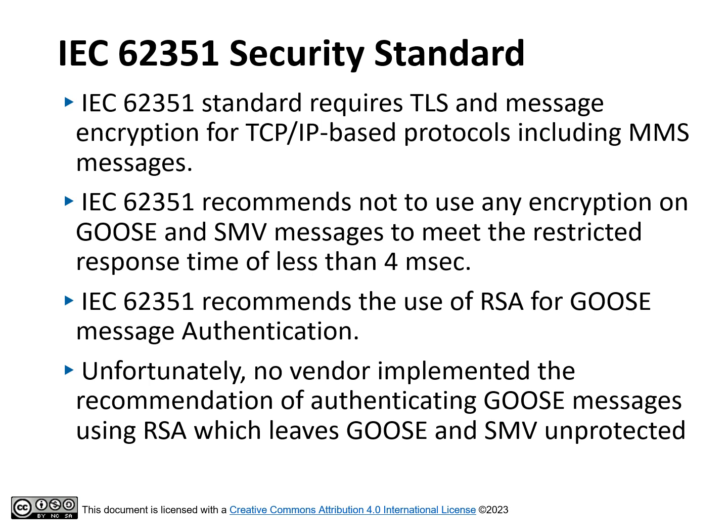IEC 62351 recommends the use of RSA for Goose message authentication. Unfortunately, no vendor implemented the recommendation of authenticating Goose messages using RSA, which leaves the Goose and SMV unprotected.